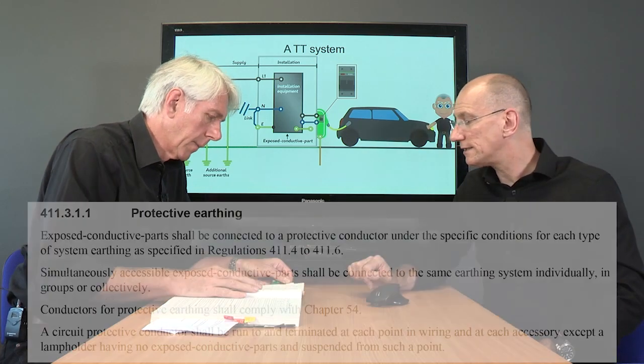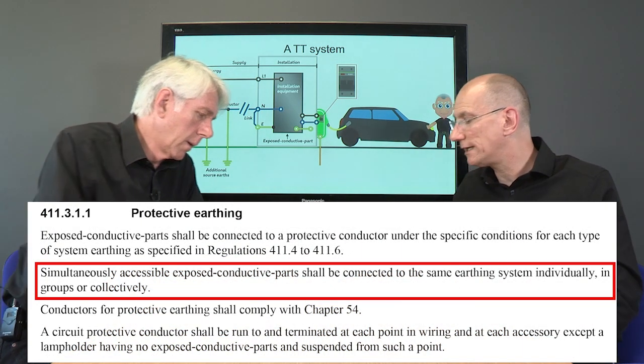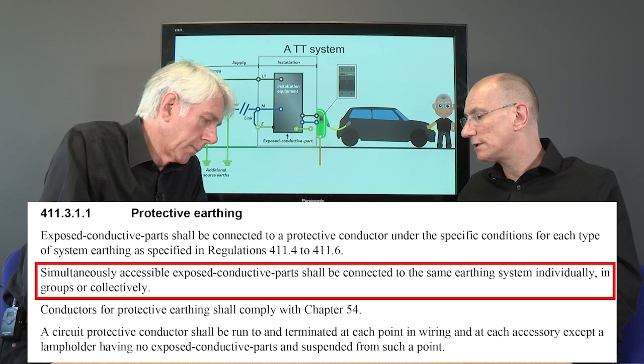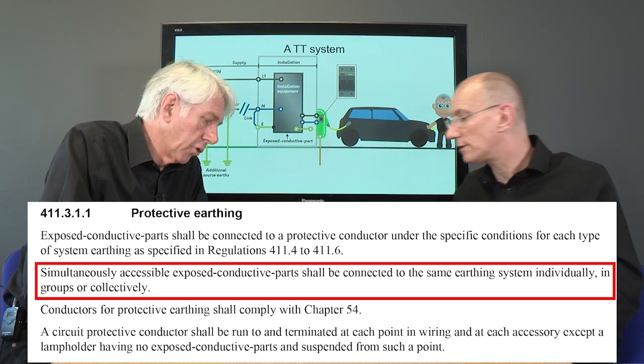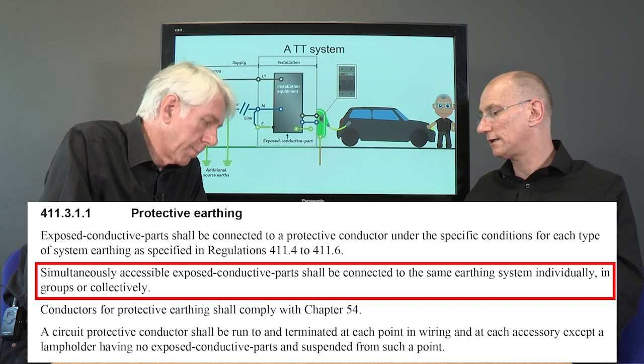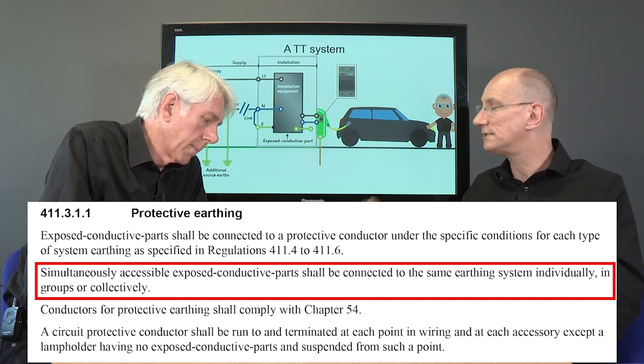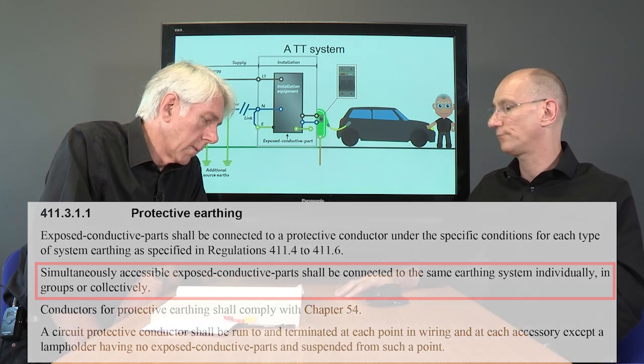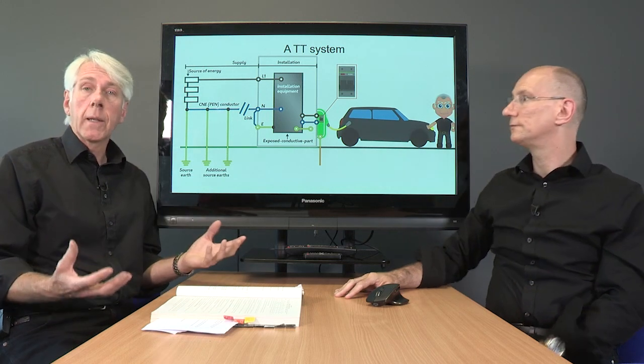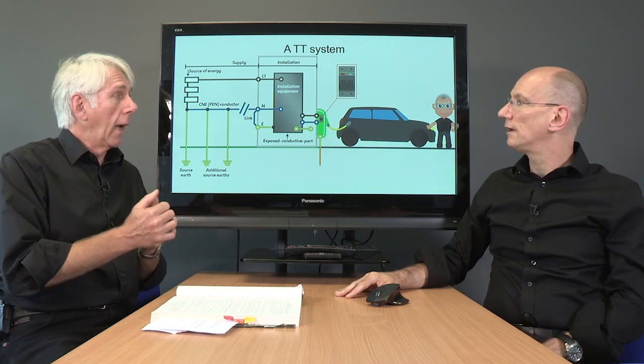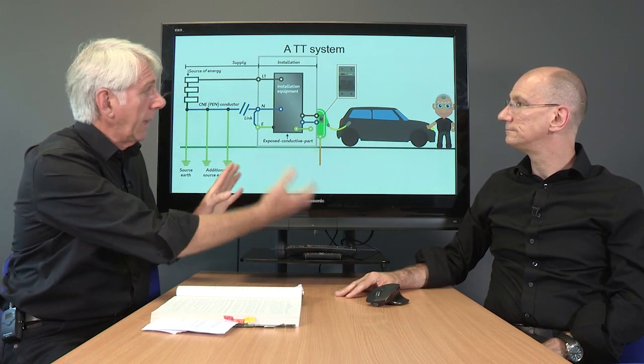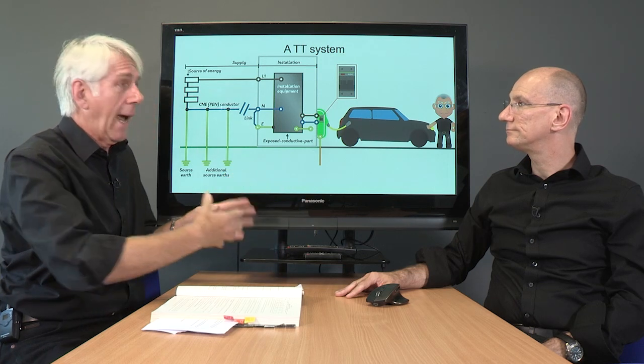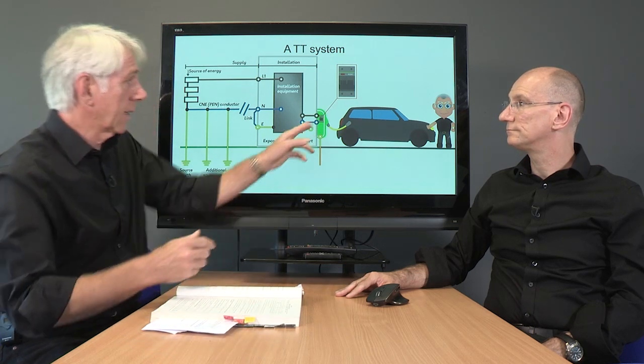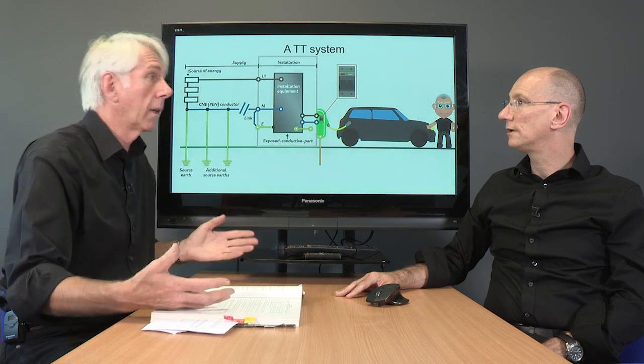All right, this is in 411.3.1.1, exposed conductive parts: simultaneously accessible exposed conductive parts shall be connected to the same earthing system. This is to avoid the possibility that you could touch the two. And you can do all sorts of speculative calculations about how big that distance must be. You know, if this charging cable is up to 10 metres, maybe.